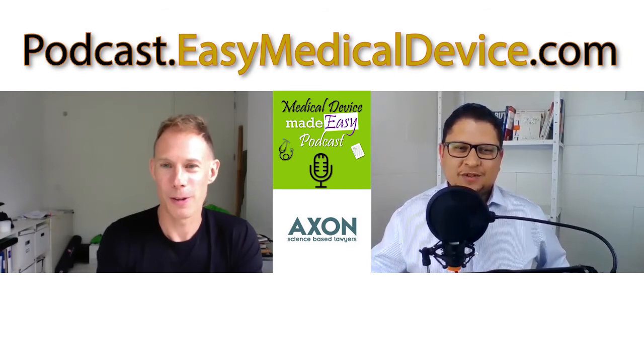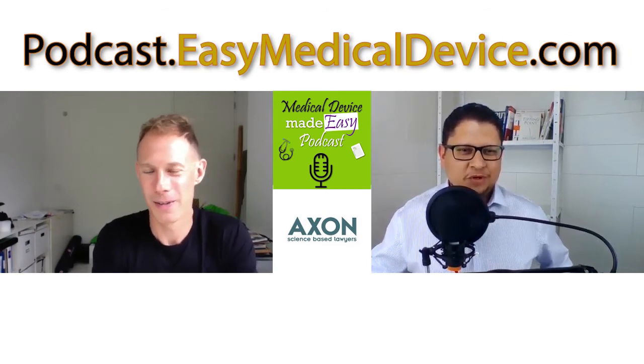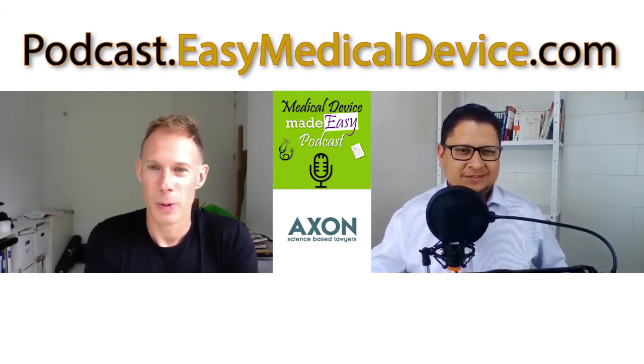And so again, you need to have then some power to execute his job. Well, yeah, and also he needs to be, or she needs to be able to monitor if the people that do the root cause analysis and so on are being quick enough. Because another innovation of the MDR is that it cuts the longest reporting deadline in half. And I've seen clients struggle with the 30 days already, so they are going to have a really big difficult time under 15 days. So we come back then to the structure.